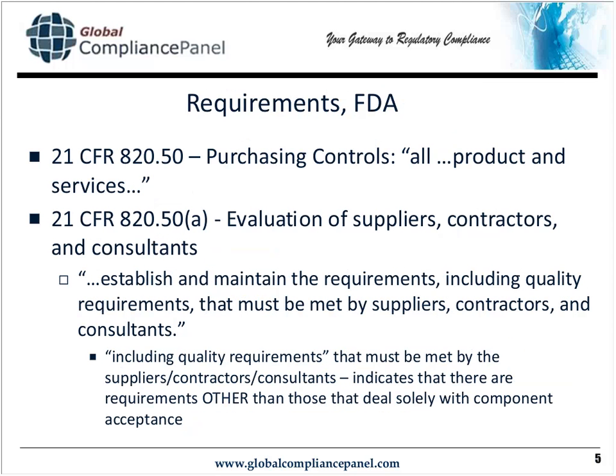That's something to pay close attention to. When it comes to domestic requirements, the purchasing controls in 820.50 talk about all product and all services, without distinguishing between types, other than implicitly saying it's product or services that go on, in, or with the device, or are used to assemble, test, or inspect the device. An example of something that does not fall under purchasing controls would be your office supply company.